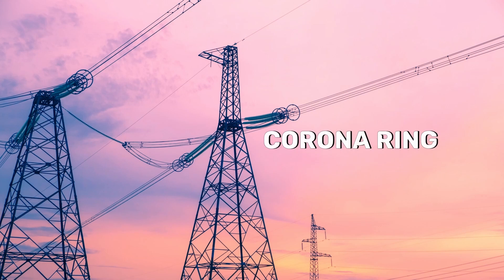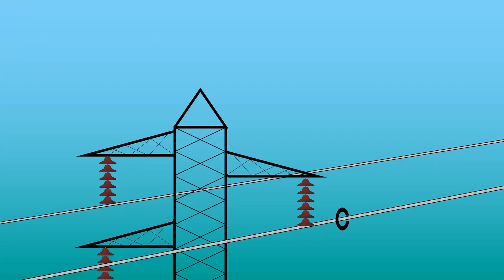Corona can also be decreased by using corona ring. It is electrically connected to the high voltage conductor encircling the points where the corona discharge may occur. This significantly reduces the electric field intensity at the surface of the conductor.